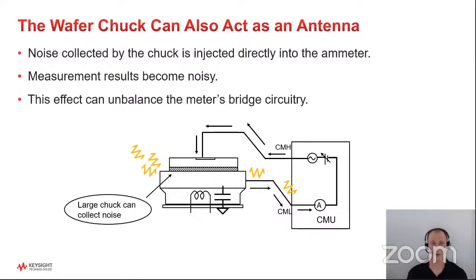There's actually a second reason that you also shouldn't connect the high side to the DUT when you're making measurements. And that's because not only is that wafer chuck a giant capacitor, it's also a pretty good antenna. And it can pick up a lot of stray electromagnetic noise. So if you connect it up as shown here with the high side to the DUT, it can inject that noise right into your low side, into the ammeter, and you're going to get bad results as well. So this is just another reason why you don't want to connect the high side to your DUT. You always want to connect the low side of the C meter to your DUT when you're making capacitance measurements.